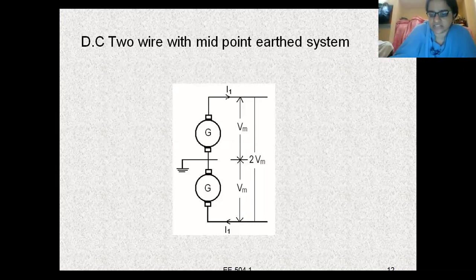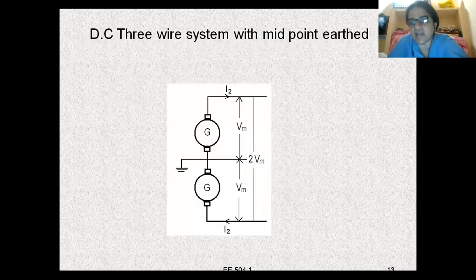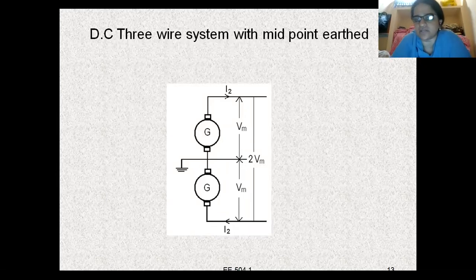Coming to the next point, DC three-wire system with midpoint earthed. As we have two generators, this is a DC three-wire system with midpoint earthed. There are two generators interconnected, and the interconnected part is earthed. The other two ends of the generators are connected to two wires, and the third wire is connected from the midpoint, which is earthed.